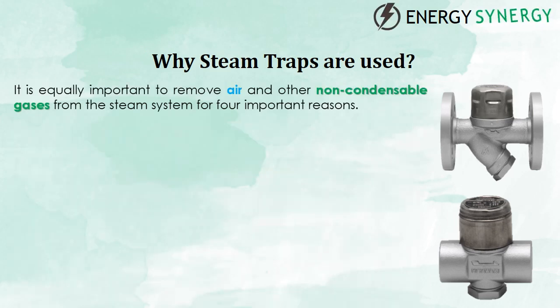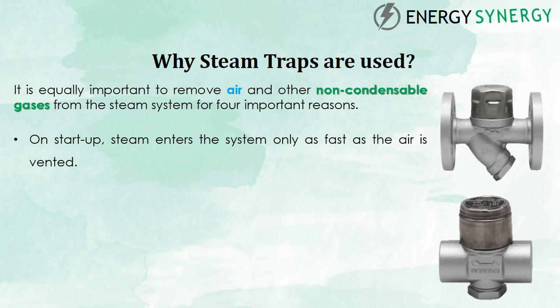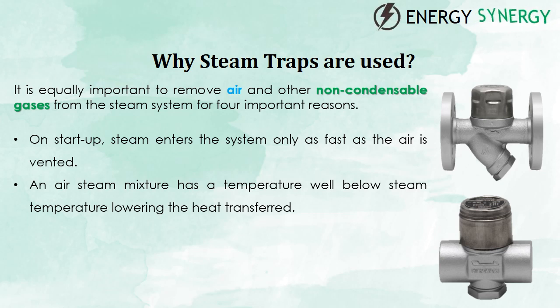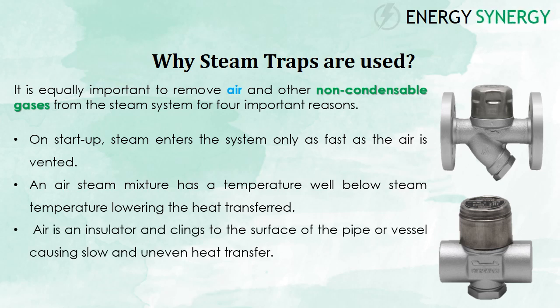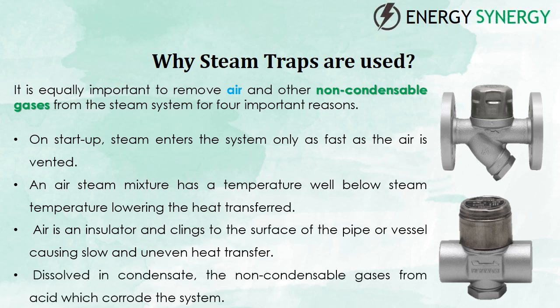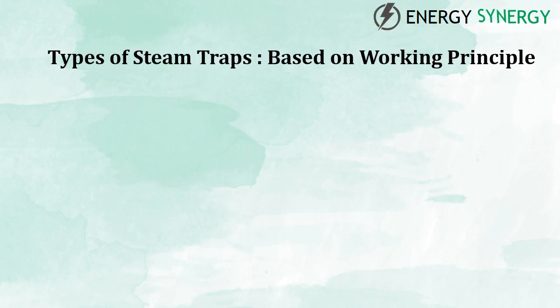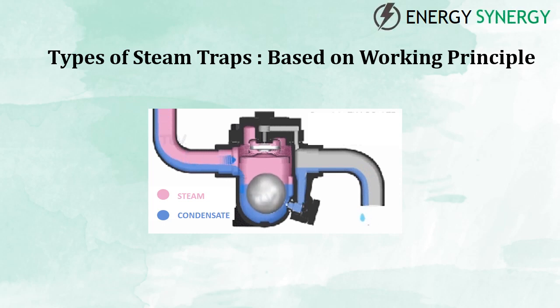It is equally important to remove air and other non-condensable gases from the steam system for four important reasons. Number one: on startup, steam enters the system only as fast as the air is vented. Number two: an air-steam mixture has a temperature well below steam temperature, lowering the heat transferred. Number three: air is an insulator and clings to the surface of the pipe or vessel, causing slow and uneven heat transfer. Number four: dissolved in condensate, non-condensable gases form acid which corrodes the system over time.